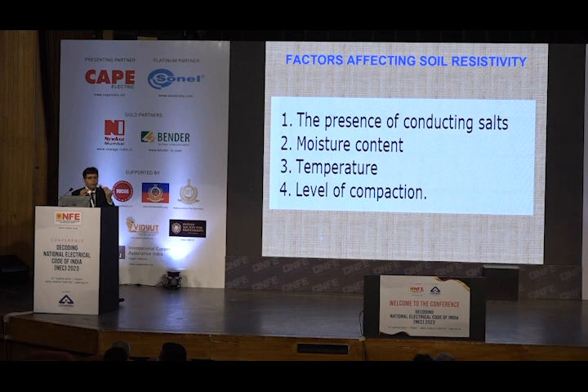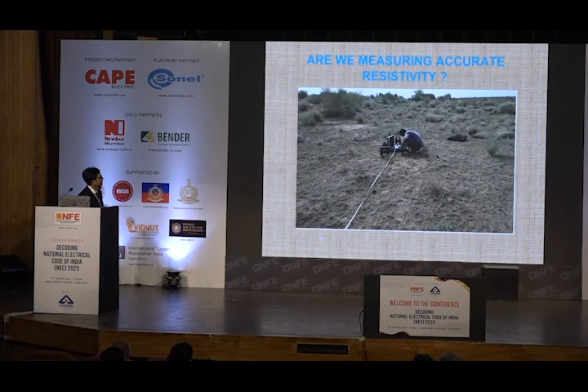Every design of earthing system starts with the very first step of measurement of resistivity, and that itself becomes important, and that depends on the presence of conducting salt, moisture content, temperature and level of compaction. A proper, accurate method is to be adopted for measurement of resistivity, because that is the backbone of your design. Garbage in, garbage out. If your measurement of resistivity is not accurate, no software can help, no method can help. Be careful.